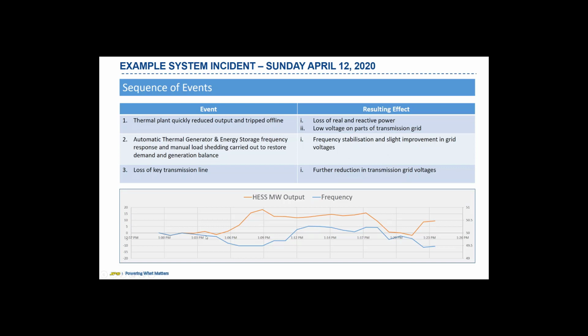So you can see from the plot, as the frequency is declining, the flywheels are trying to help. But as the decline becomes worse, then we start to get that big output from the batteries themselves. And you can see that the frequency stabilized at around 49.5, which is around where we have the set point for the batteries to kick in. So the batteries help to stabilize the frequency around this point, giving our operators a chance to bring other assets online or to take any other kind of action.